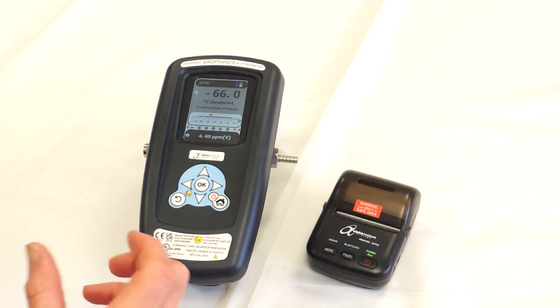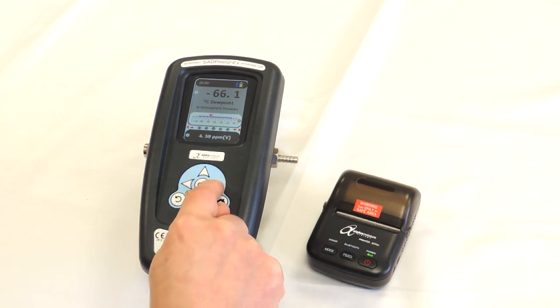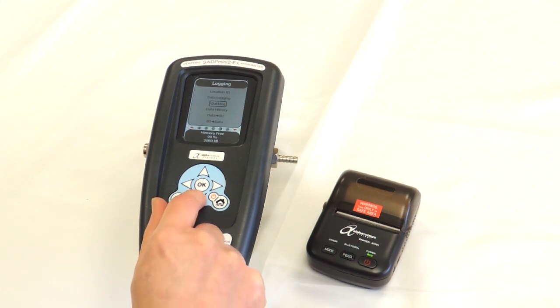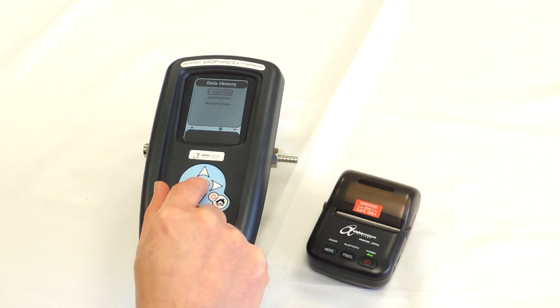We're now going to show you how to print some data from the SADP Mini 2 EX to the Bluetooth printer. Let's go to a logging screen that we've got some data previously logged on. So we go to logging first then we go down to quick log data history. We're going to go into data history and then we've got three options log data, quick log and snapshot data. We're going to go to snapshot data.